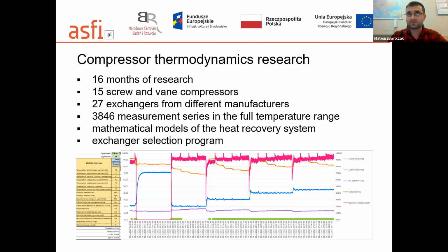In the next step, we rented 15 compressors from 6 different manufacturers. They were from Atlas Copco, Kaeser, Boge, Compair, screw compressors, and vane compressors from Mattei and Hydrovane, in 3 power ranges, 30, 75, and 110 kilowatts. And we tested these heat exchangers across these compressors.